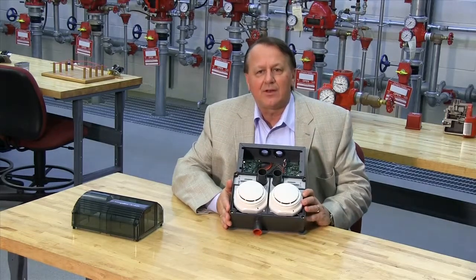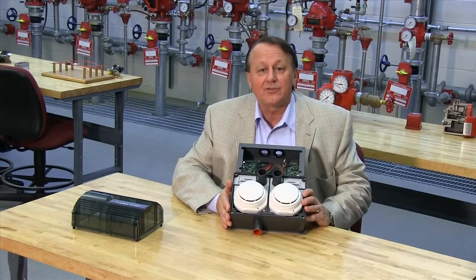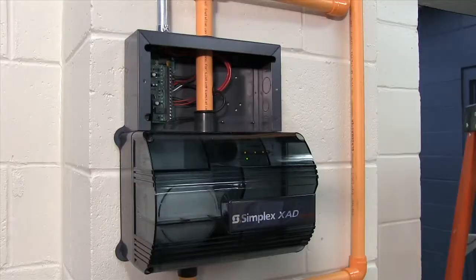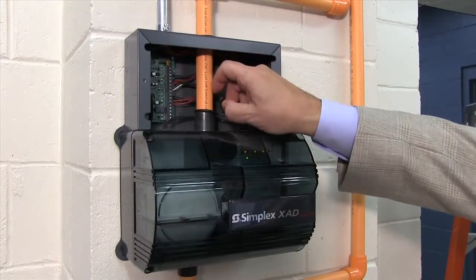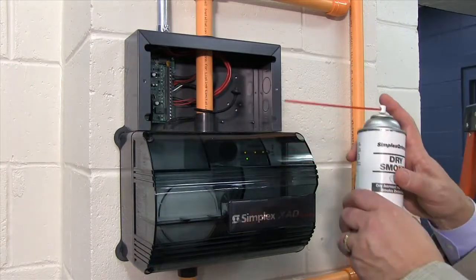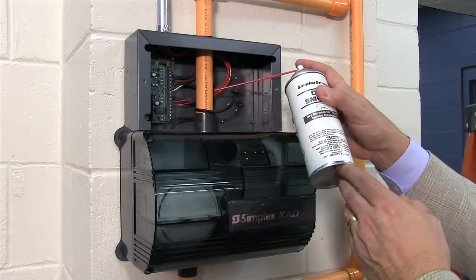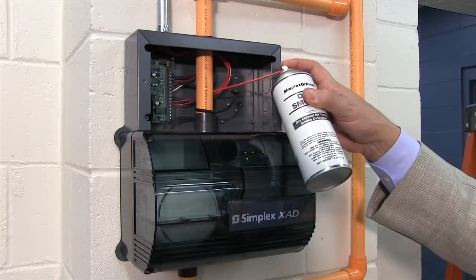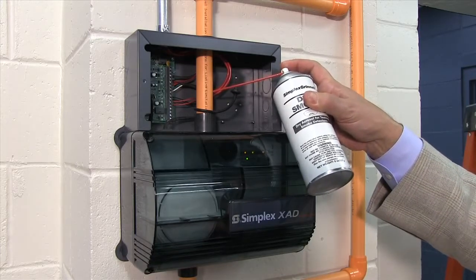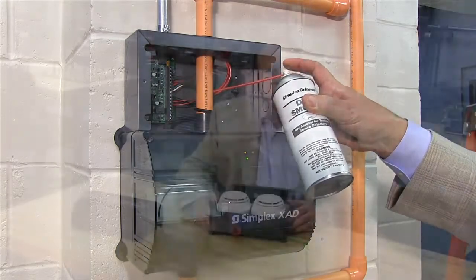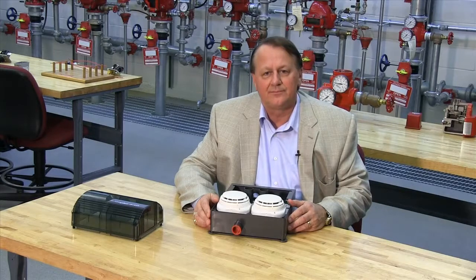Since the unit can be mounted in an easy-to-access area, it makes testing much easier. The test plug can be removed to introduce smoke-like particles from an aerosol test can. This meets NFPA annual functional test requirements, Canadian system verification requirements, and annual inspection criteria.